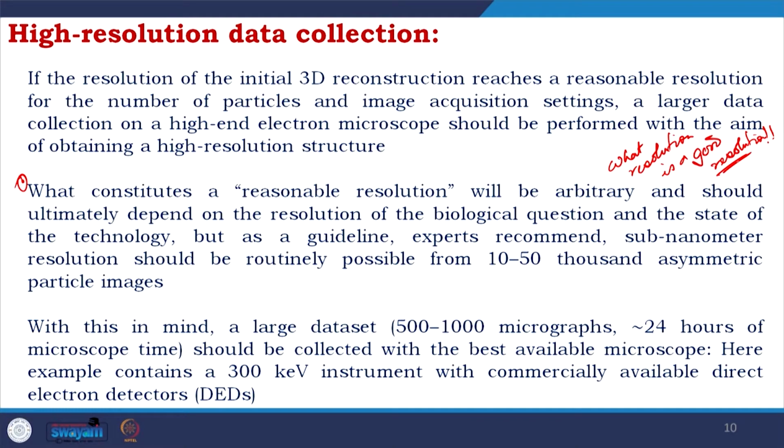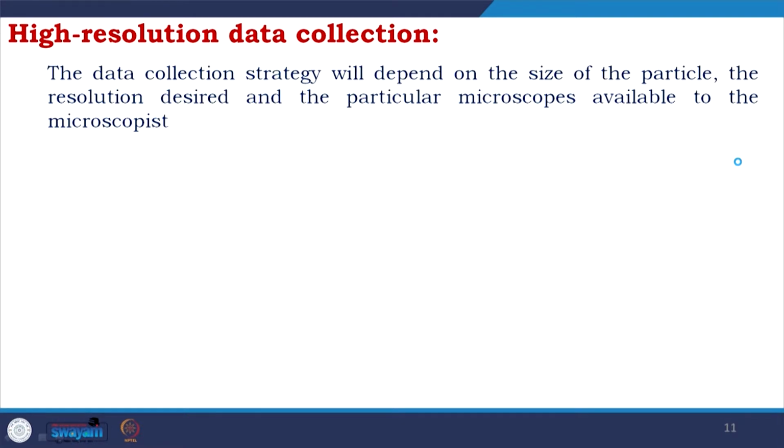With this in mind, a large data set of 500 to 1000 micrographs and 24 hours of microscope time should be collected with the best available microscope. In this study, we are talking about a 300 kilovolt instrument with commercially available direct electron detectors or DEDs. The data collection strategy will depend on the size of the particle, the resolution desired and the particular microscope available to the microscopist.